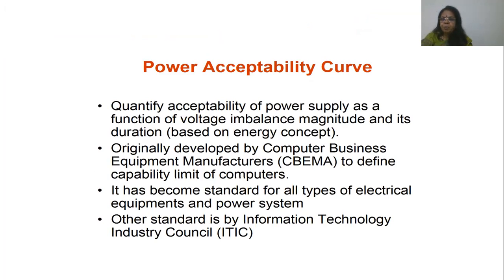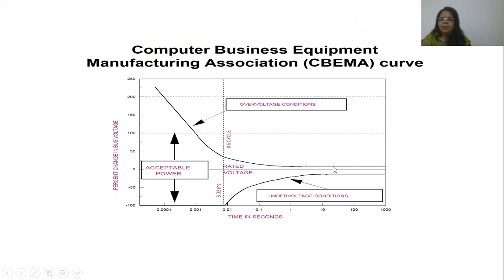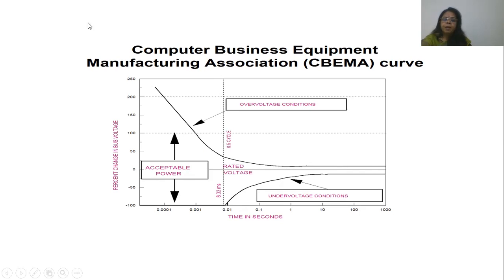Power acceptability curves define how we know if the quality of power is acceptable. These are defined by CBEMA (Computer Business Equipment Manufacturers) and the Information Technology Industry Council (ITIC), as these represent the most sensitive equipment. The CBEMA curve has two boundaries on a plot where the y-axis is percentage change in voltage and the x-axis is time on a logarithmic scale (from 0.0001 second up to 1000 seconds).